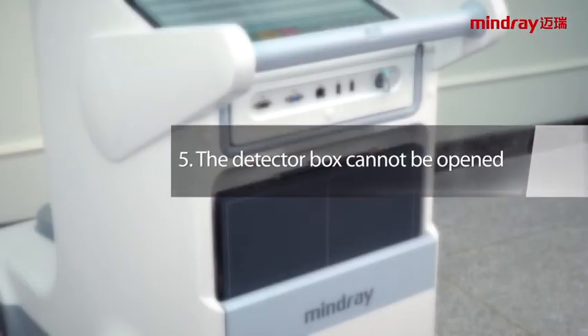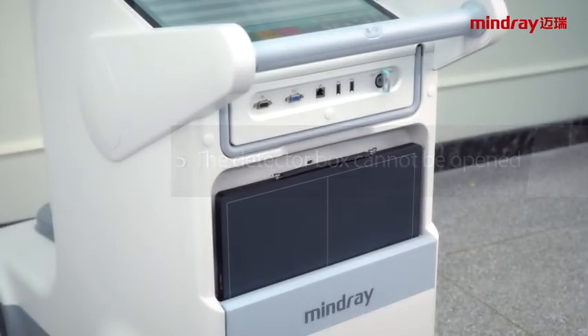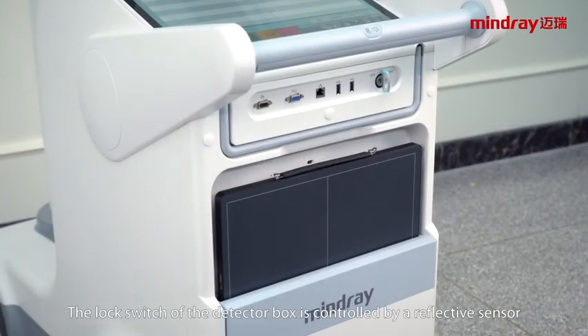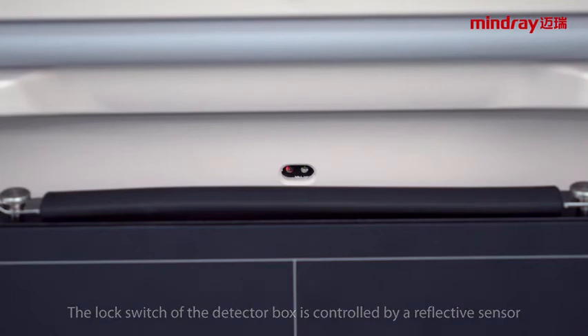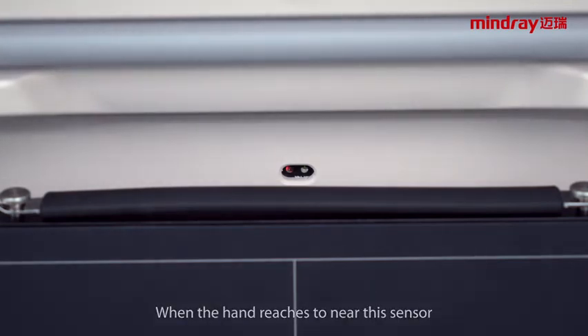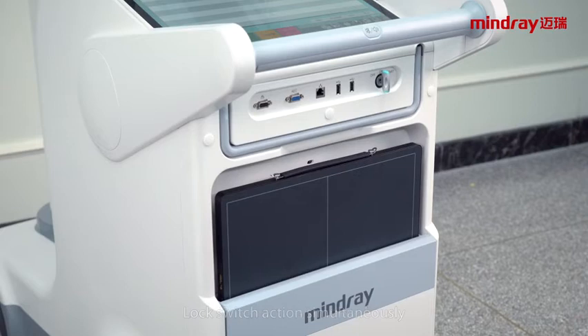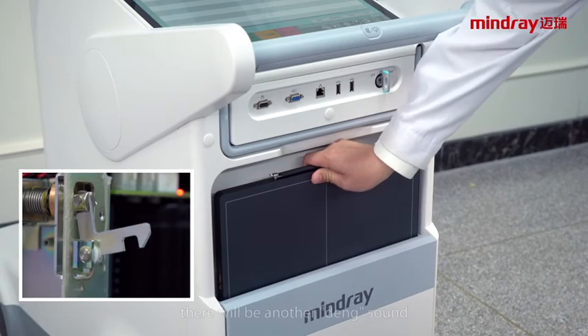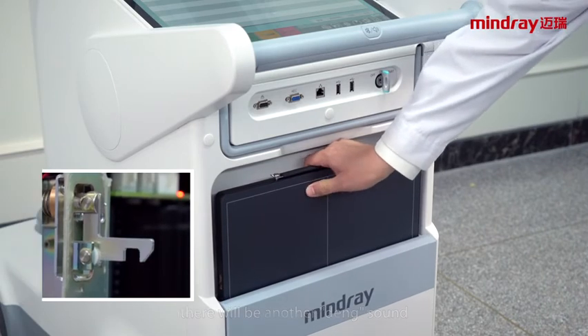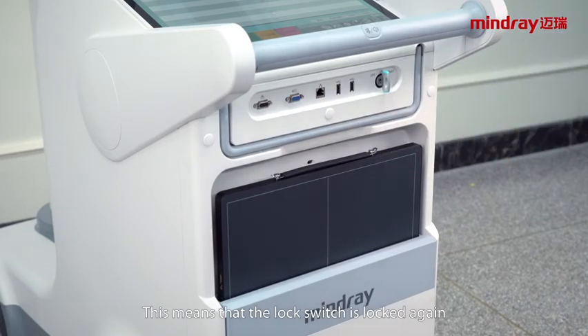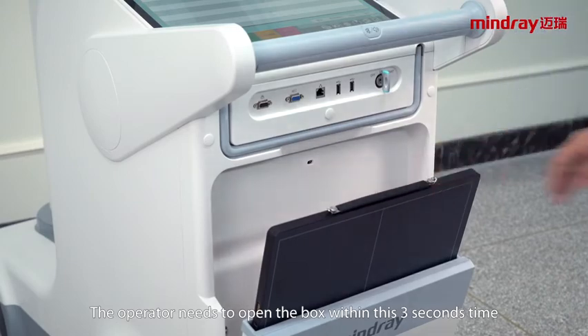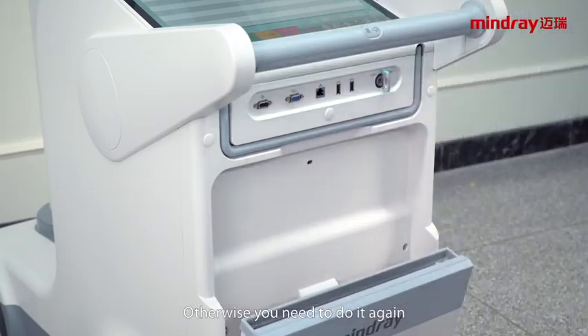The detector box cannot open. The lock switch of the detector box is controlled by a reflective sensor. When the hand reaches near this sensor, the sensor is triggered. The lock switch acts simultaneously. There will be a ding sound when unlocking the box. After about 3 seconds, there will be another ding sound. This means the lock switch is locked again. The operator needs to open the box within this 3 seconds. Otherwise, you need to do it again.